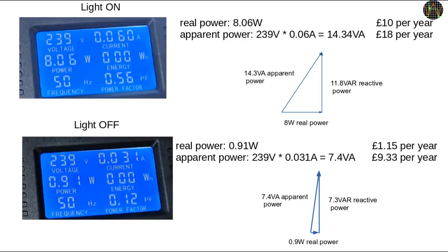You can get apparent power by dividing the real power by the power factor or in the case of my power monitor you can also multiply the volts and ampere readings for the same result. The power factor is the cosine of the angle between the real power and the apparent power.